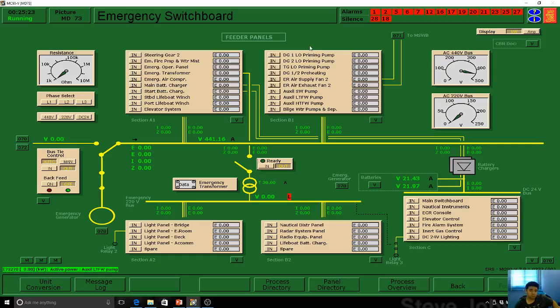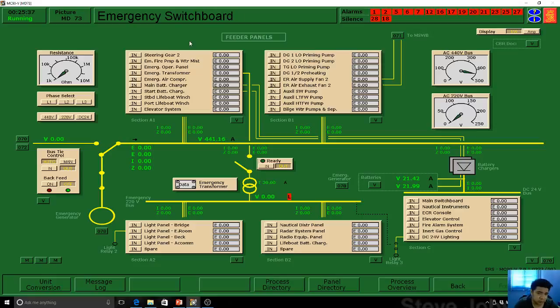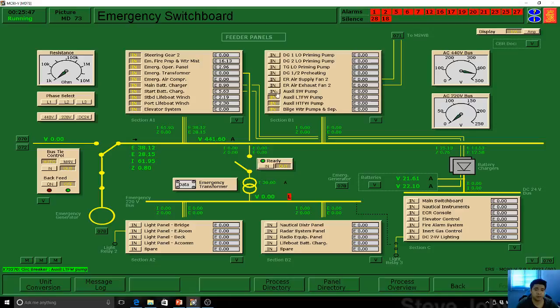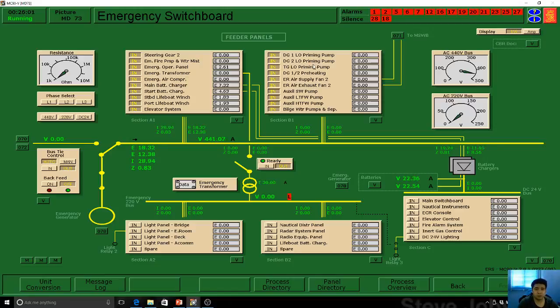Going to the emergency switchboard — you have feeder panels and an emergency transformer for the 220 volts. On the emergency switchboard you have steering gear number two, fire pumps, and everything. You can switch all on because the emergency generator can carry all those loads, including the elevator, port and starboard lifeboat, and everything regarding emergency starting. Some ships only start with generator number one; other ships use both generators. This simulator has diesel generators one and two, with preheating — possible to start the generator from the switchboard.